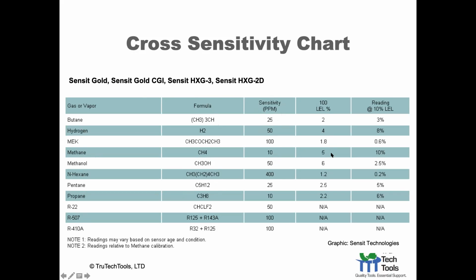You can see methane's 5, propane, they rounded up from 2.15 to 2.2. And then at 10% LEL, this is actually the reading you would see on the screen. So at 10% LEL, you would see about a 6 on your HXG-2D for propane. So just, again, this is awareness that if you're measuring propane, you're going to have in mind a lower number than 10% when you're at the 10% LEL level.